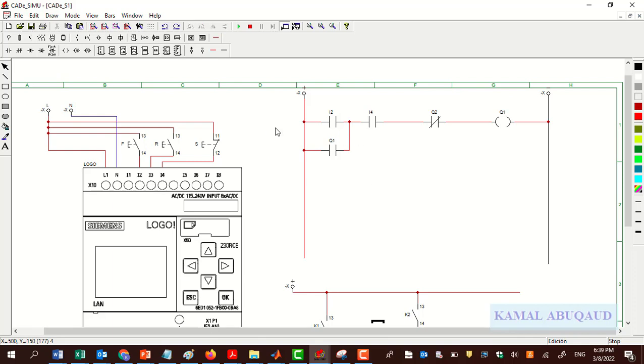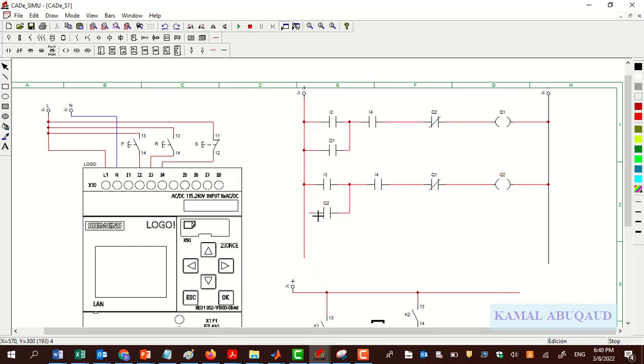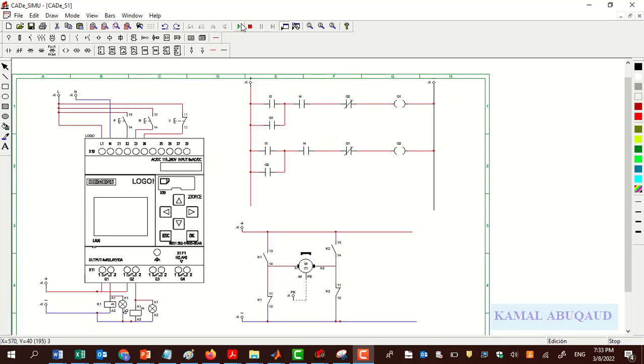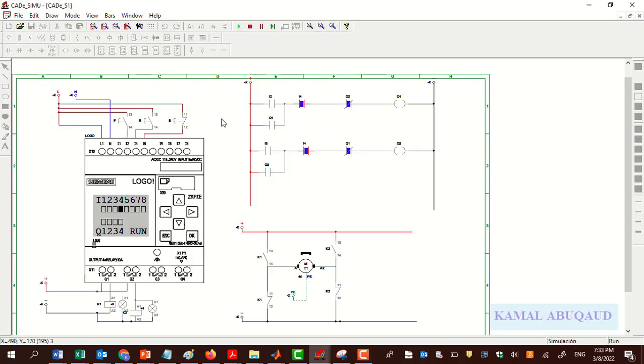I'll do the same thing for the reverse direction. Then I run the simulation and check the circuit behavior. The forward button runs the motor in the forward direction and the green light is on. The stop button turns off the motor. The reverse button runs the motor in the reverse direction and the yellow pilot light is on.